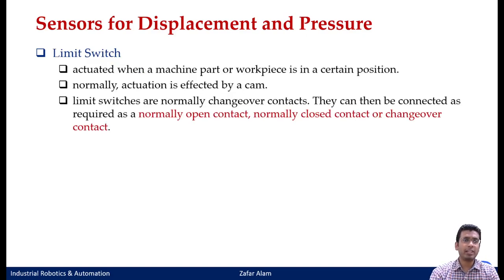Since we are working in a pneumatic or hydraulic range, sensors are also used to measure pressure in the line, as many activities will depend upon the pressure in the circuits. To detect position or distance, the first type of sensor we use is the limit switch. A limit switch is actuated when a machine part or workpiece is in a certain position — the actuation is normally effected by a cam, meaning you have a physical contact. Like your roller valve in a pneumatic circuit, limit switches can also be normally open, normally closed, or changeover contact type, but they output electrical signals instead of pneumatic signals.